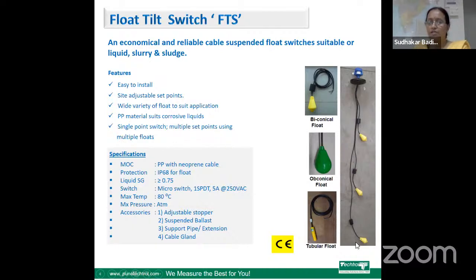On the right hand side, you can see the picture of the level switch, which is integrated with 3 level switches with the flange connection and enclosure. The float is IP68, so it can be submerged into the liquid. It is suitable for minimum specific gravity of 0.75. The output of this switch is micro switch, 1 SPDT, 5 ampere at 250 volt AC contacts. Maximum temperature is 80 degrees Celsius and pressure is atmospheric.